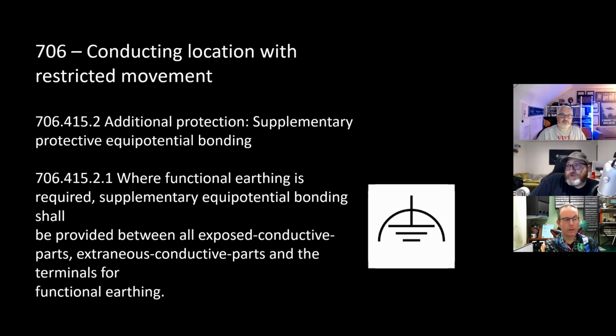706, conducting location with restricted movement. They've just added a bit of supplementary bonding. So you've got here 706.415.2, which is a supplementary bonding form of additional protection. It basically means we're using Earth for functional purposes a lot lately. And if we're in this location and the earthing around us, or there's any earthing around us that is used for functional purposes, we need to cross-connect and supplementary bond the crap out of it.